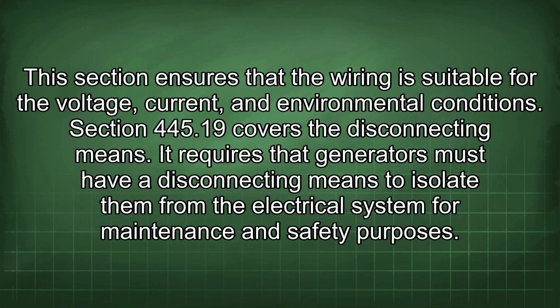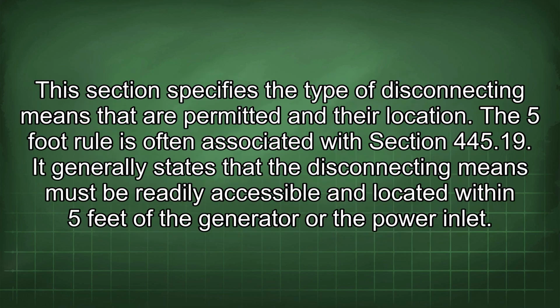Section 445.19 covers the disconnecting means. It requires that generators must have a disconnecting means to isolate them from the electrical system for maintenance and safety purposes. This section specifies the type of disconnecting means that are permitted and their location.